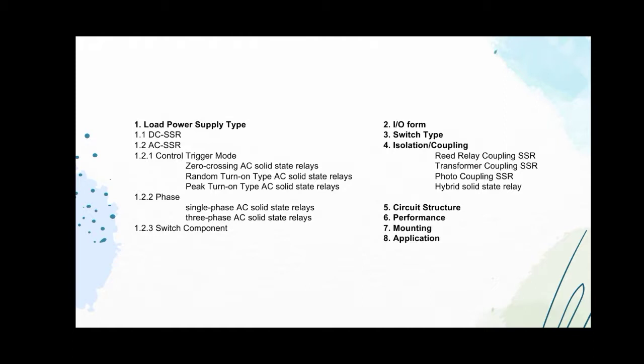The type of load power supply is the DC SSR and AC SSR. And control trigger mode: the types are zero crossing AC solid-state relays, random turn-on type AC solid-state relays, and peak turn-on type AC solid-state relays. The other is the phase of the load power supply, and the types of phase are single-phase AC solid-state relays and three-phase AC solid-state relays. Another type of load power supply is the switch component. The other type of solid-state relays is by input and output form, switch type, and isolation coupling. The types of isolation coupling are reed relay coupling SSR, transformer coupling SSR, photocoupling SSR, and hybrid solid-state relay. And number 5 is circuit structure, performance, mounting, and application.